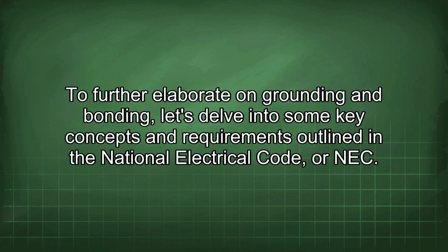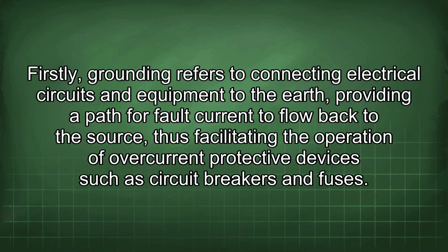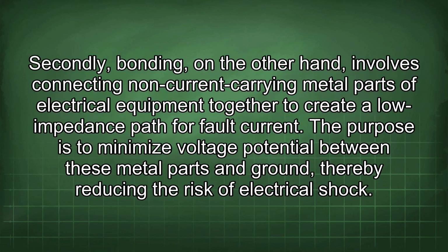Code, or NEC. Firstly, grounding refers to connecting electrical circuits and equipment to the earth, providing a path for fault current to flow back to the source, thus facilitating the operation of overcurrent protective devices such as circuit breakers and fuses. Secondly, bonding, on the other hand, involves connecting non-current carrying metal parts of electrical equipment together to create a low impedance path for fault current. The purpose is to minimize voltage potential between these metal parts and ground, thereby reducing the risk of electrical shock.